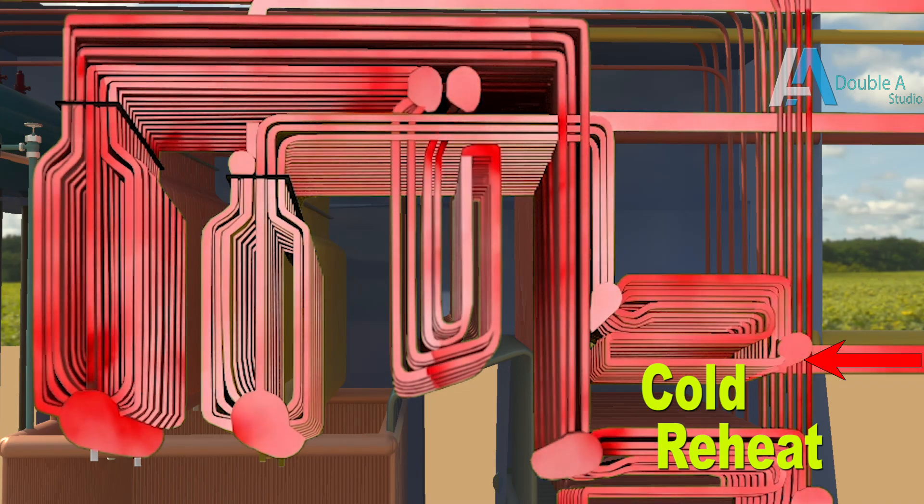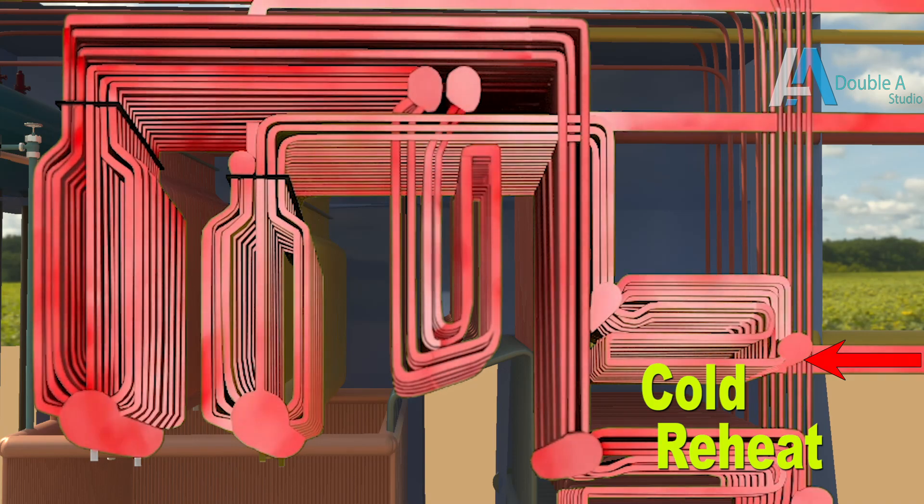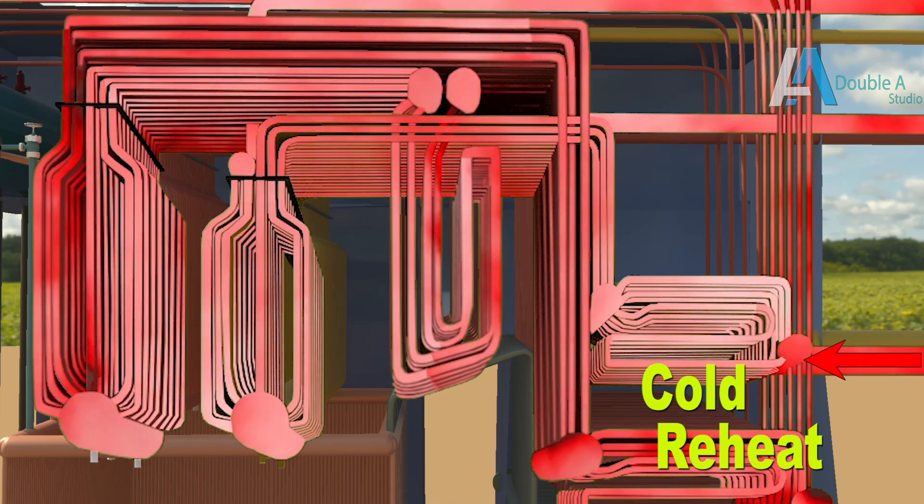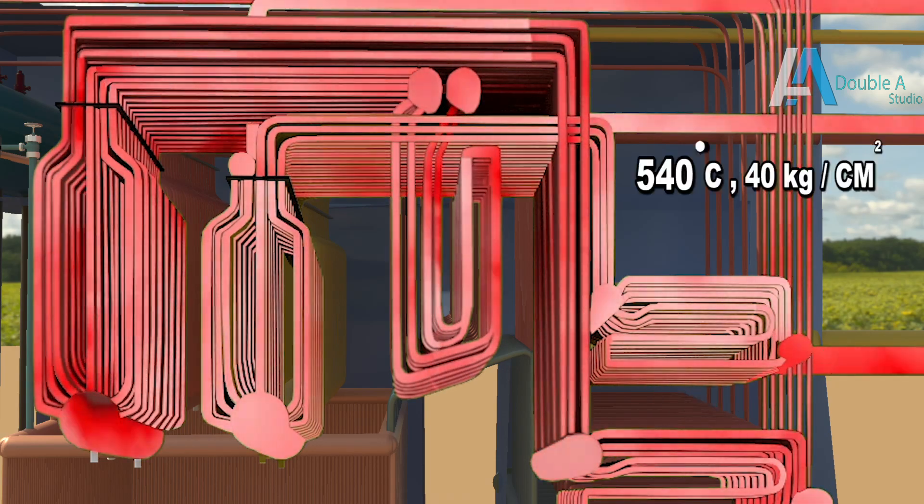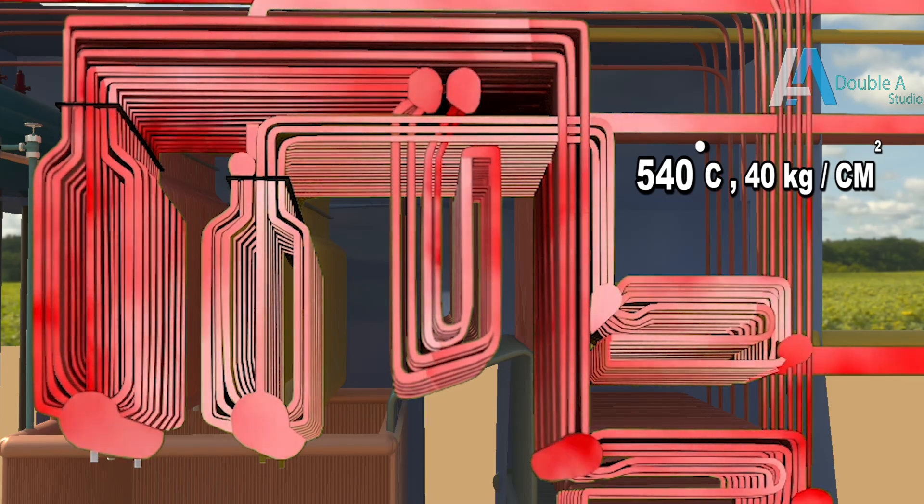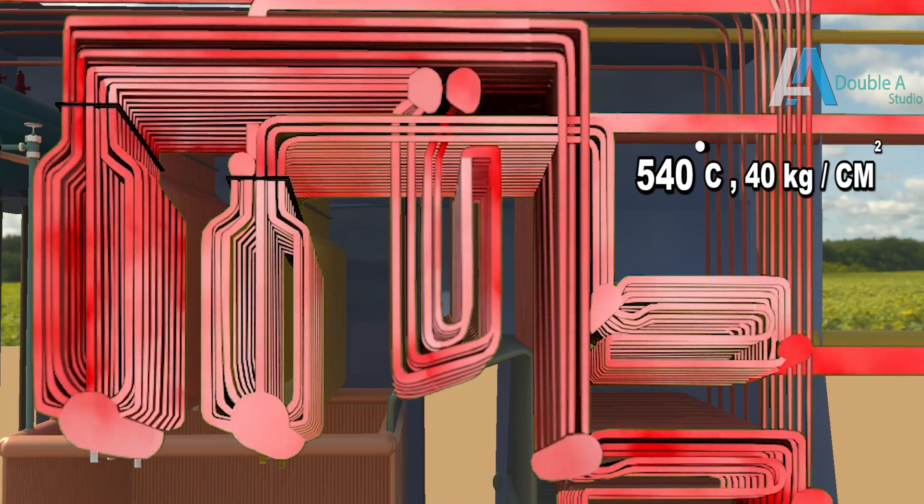After primary reheater steam is sent to final reheater for further reheating. Reheater increases temperature of steam at same pressure, that is, temperature of 540 degrees centigrade and pressure of 40 kilogram per centimeter square. This reheated steam is called hot reheat.